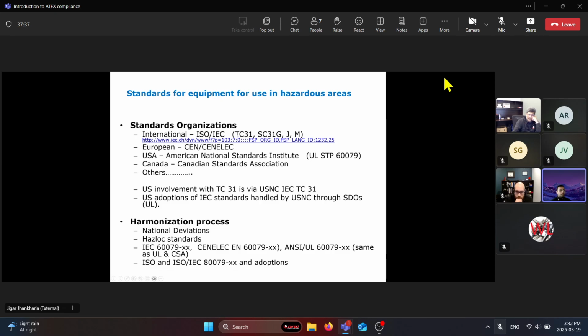TC31 is the committee for the IEC 60079 standards. I'm not sure if any of you worked with our previous senior engineer, Mark Koppler. He used to be a committee member, one of the executives on the TC31 committee before he retired 2 years ago. So coming back to the harmonization process, national deviations is what we talked about, that it's adopted from the IEC 60079 standards, and the CENELEC EN 60079 standards are adopted from the IEC, same with the UL and CSA standards.